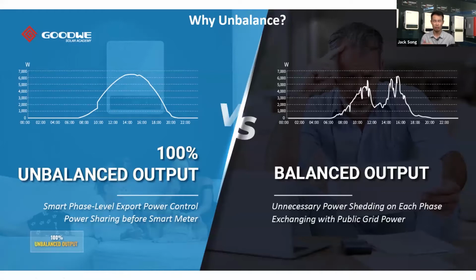Okay, of course, like all three phases, the max output on phase 1 to the grid or to charge the battery is 2 kilowatts. The lowest power is on phase 3, for example, 0.5 kilowatts to charge the battery or support the loads, right? But without the unbalanced function, the production on all three phases has to follow 0.5 kilowatts. So on phase 1 and phase 2, they have to limit the production of the solar systems. Generally we can see in the diagram that with the unbalanced output function, the production from the solar can be as high as possible. It can maximize the solar production, and without the unbalanced function, the solar production will be limited like this.